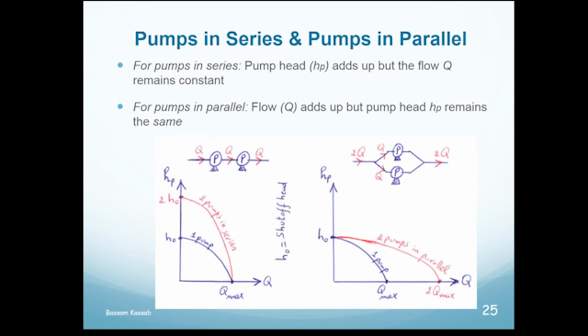As I've shown you here in the diagram that I drew manually, you can put 2 pumps in series. And when you put the 2 pumps in series, let's see what happens to your pump curve. Here in blue, you can see the pump characteristic curve for one pump. But when you add another pump in series, you are going to get more head out of this pump, but for the same flow, because the same Q is still going through the pump, theoretically. So when you have one Q here, it gives you this head if you have one pump. But the same Q, if you add another pump, will give you double the head. So even the shutoff head will double. Every point here on the pump curve will double. So that's how you plot the new pump curve for 2 pumps in series.